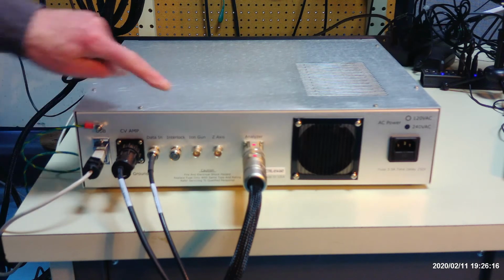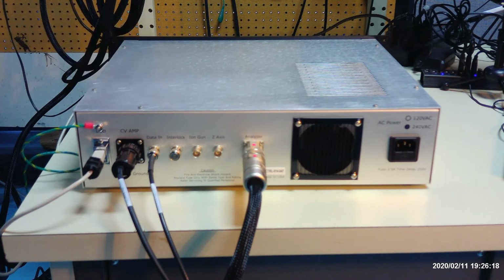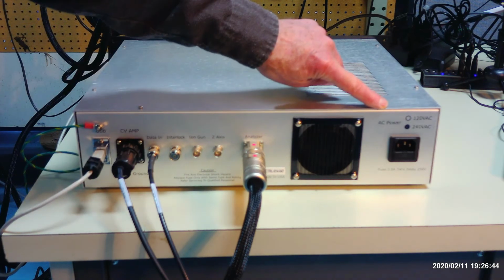Alright, the ion gun is a remote connector that can be set to either TTL high or TTL low to turn your ion gun on if you want to do sputtering. The Z-axis BNC is reserved for future use. We're going to have a possibility to automate the Z translator to move up and down automatically. So far, however, the manual ones are working just fine, but we did design the controller with that feature in mind for future development. Last but not least, we have the AC power connection over here.